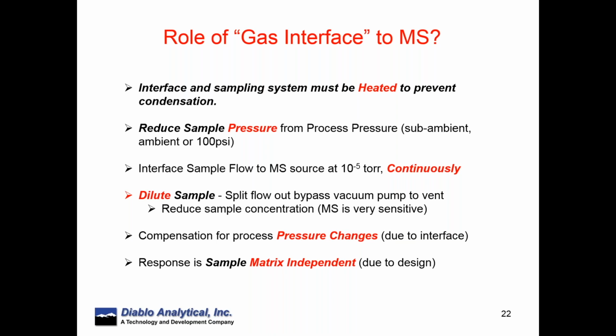Then mass spec, unfortunately, is not only a concentration detector, but it is a pressure detector. So if we have pressure changing in our process, that induces changes in what looks like the signal level, and we have to deconvolute the pressure changes from the concentration changes. And then, of course, we need our response to be matrix independent. We want to be able to calibrate with a gas mixture in, for example, helium, and apply that external standard calibration to our process gas with all the matrix present.